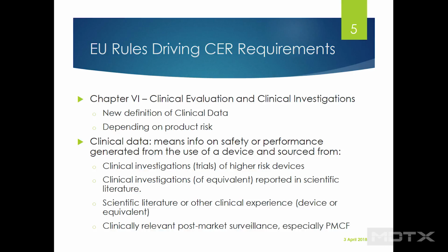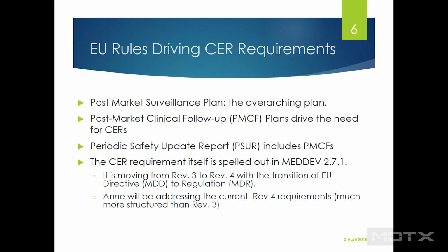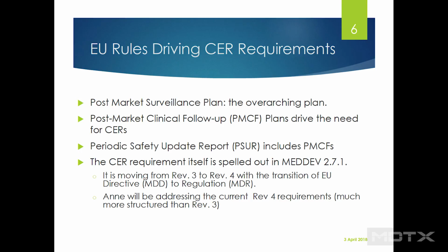You can also have scientific literature about your device or an equivalent, and in addition to the scientific literature, there can be clinical experience. Think of that as separate from studies and investigations conducted on your equivalent devices or your device. There's also clinically relevant post-market surveillance. For me, this is the foundation of everything, because this is what's changing across the globe, which is why the presentation was subtitled changing post-market data, especially in the context of the PMCF. We're going to talk about that.